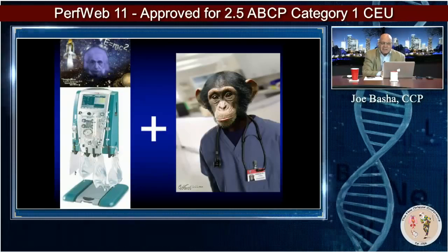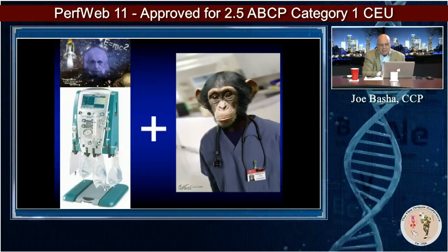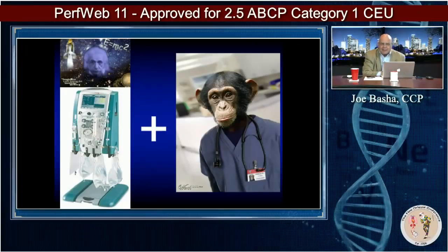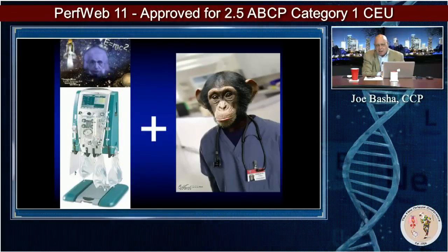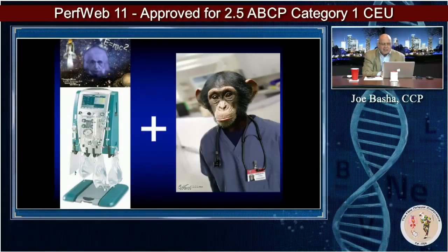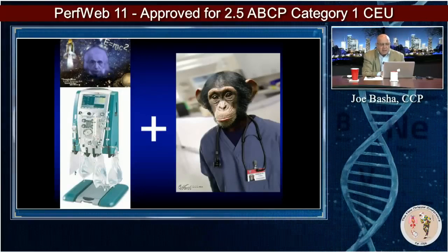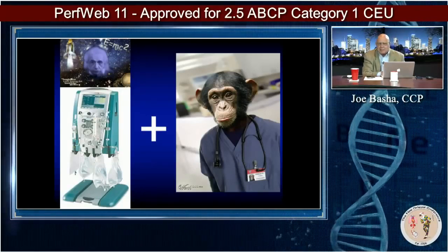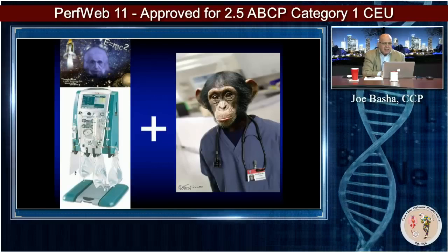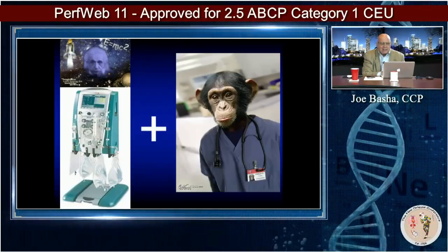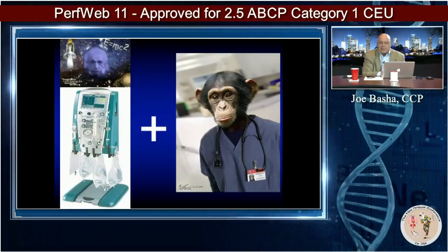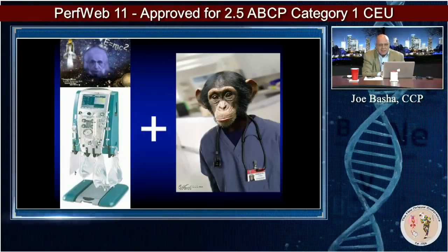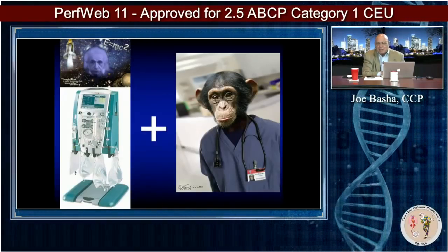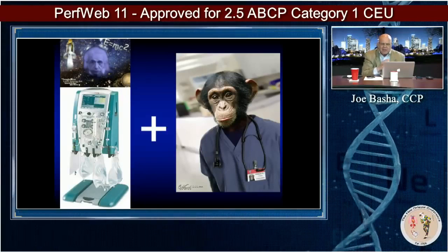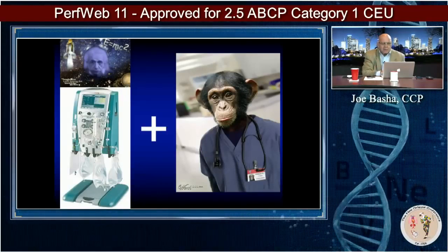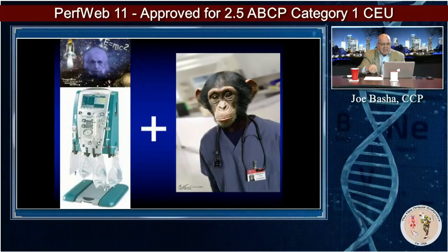Or the system is going to alarm. So I see that as an advantage, but if you bump it, that makes it alarm and shut off, and you have to reset it. If the scales go bad, it's going to be a problem, and you need to recalibrate them. You're changing bags. The physical labor intensiveness of this particular device is much higher than another one I'm going to show you.